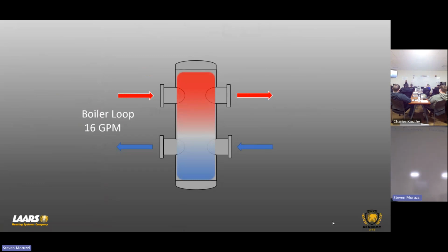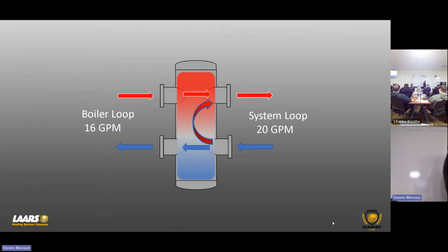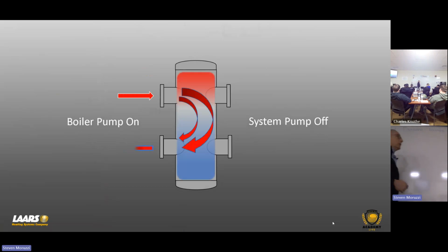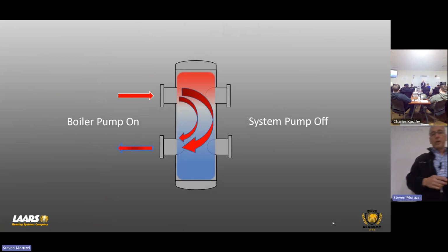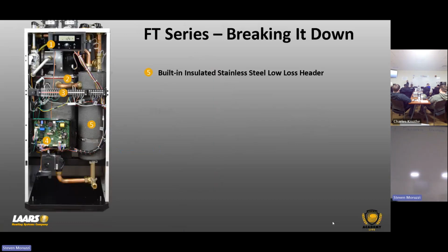In this next example, I still have 16 GPM on my boiler pump, but maybe I got 5 zones out in that system. We had a power outage or what have you, and all zones came on. What would happen? I have a higher flow rate on the system in that example. All right, so this is how a low loss header works, and it's built right in. And we had talked about something called pump post purge. So at the end of my call for heat, I'm running that pump for 30 to 60 seconds, very simply through the low loss header and back to the boiler, okay? So that's how that low loss header works.